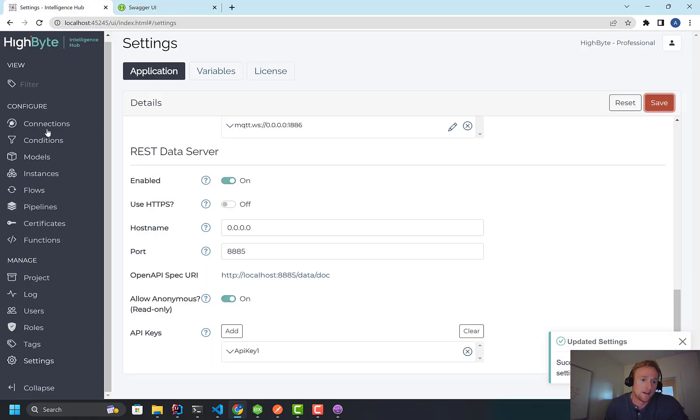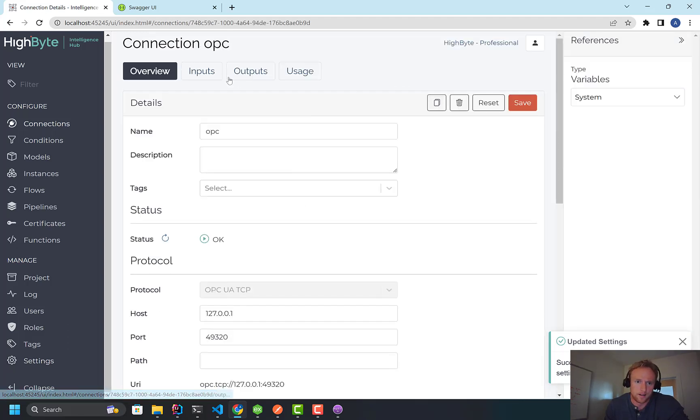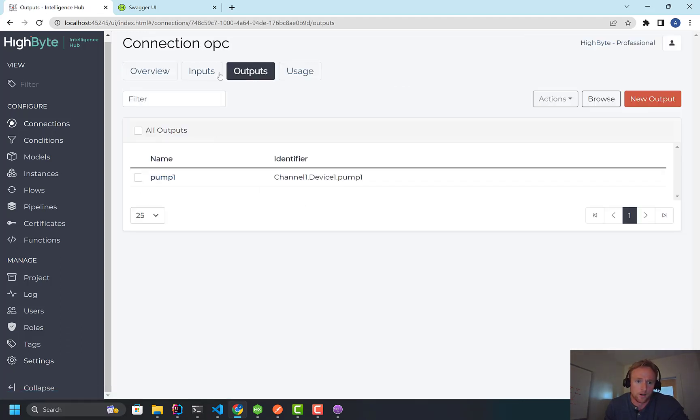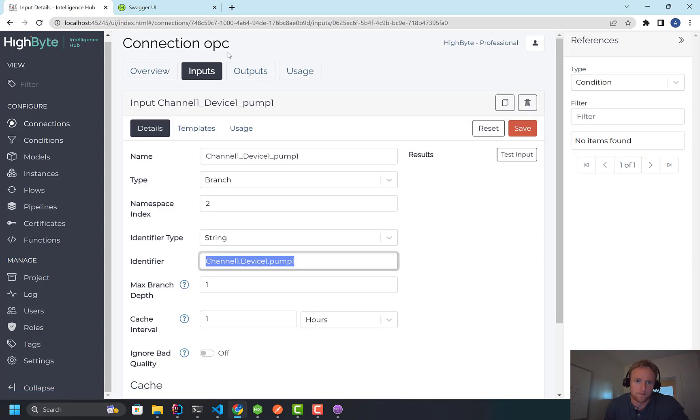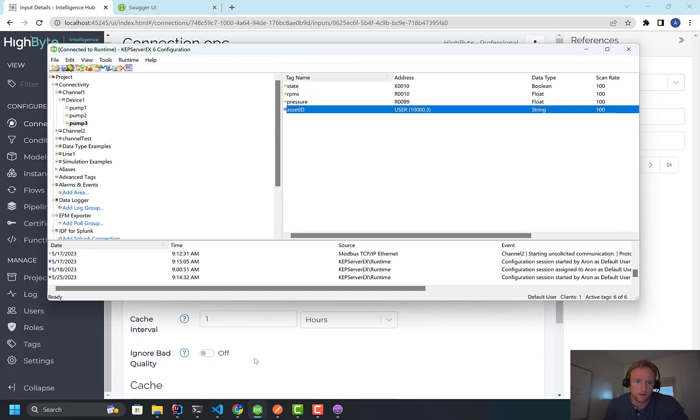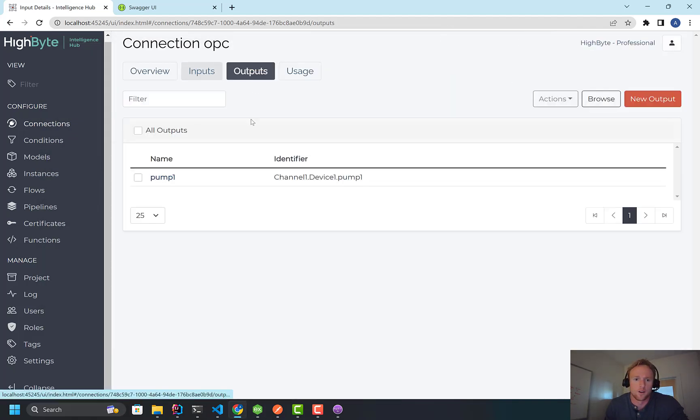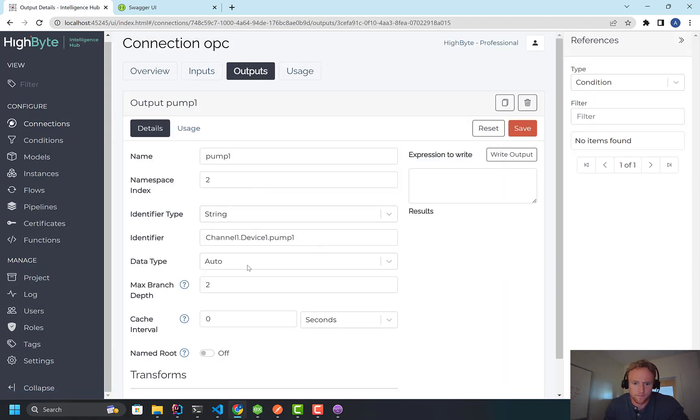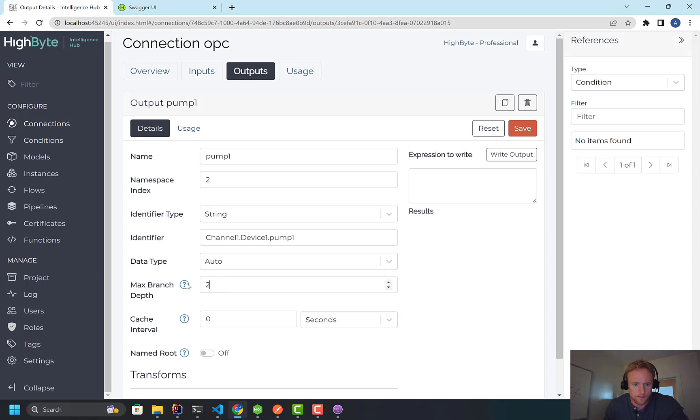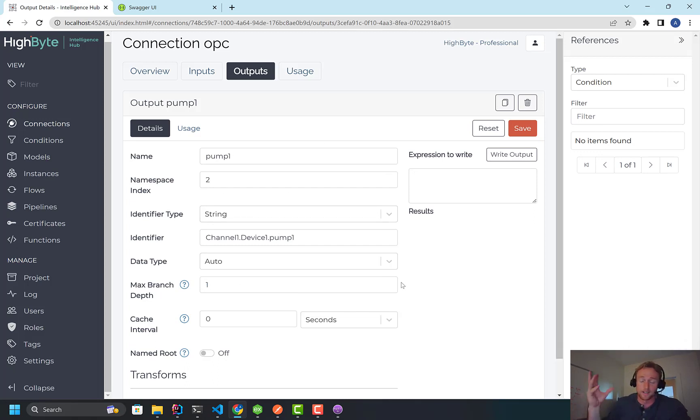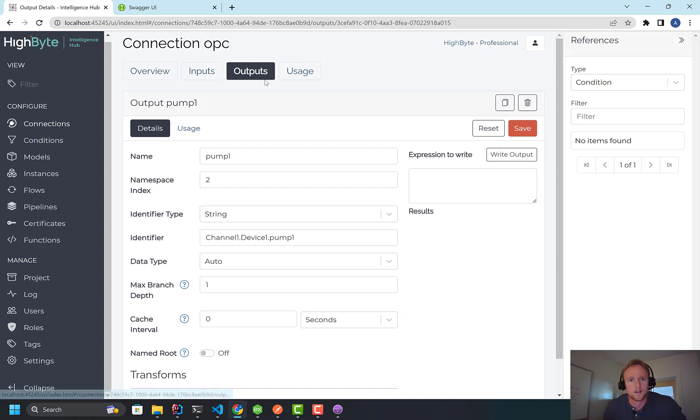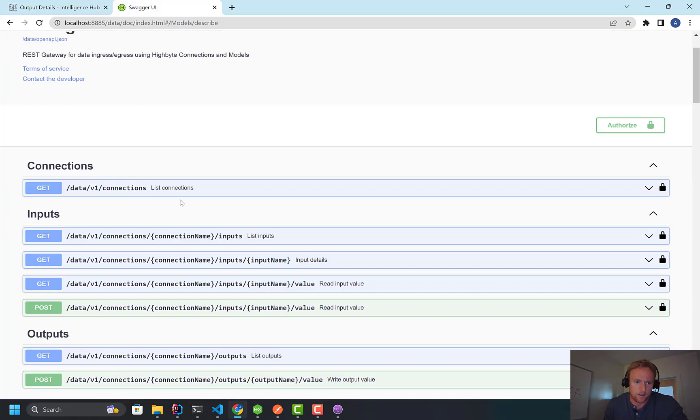So I'm going to go back to this API. And in here, I'm going to put the authorization token up here. And I'll show you how to do this in Postman too. So you can kind of see what the query looks like. Now in HighByte, for OPC, if I want to write out to OPC, I need an output. So I've already created one. So you can see my input is targeting pump 1, that identifier in the OPC server. If I pulled up Kepware, that's this one. So I'm going to create an output that targets the same thing. And I think I'm going to set it to auto-discover. So it's going to look at this branch and then issue a write. It's going to take the JSON and translate it into OPC. But I need the output.